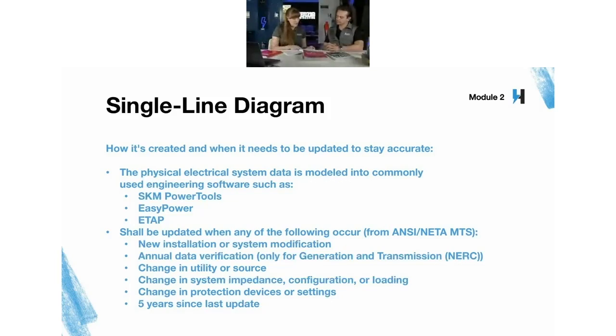In fact, in 205.2 of the NFPA 70E, where it talks about the need for single line diagrams, it shall be maintained in legible condition and shall be kept current. There's no timeline - it's just anytime there's a change, keep it current, because everything else we're talking about is reliant on an accurate one-line.